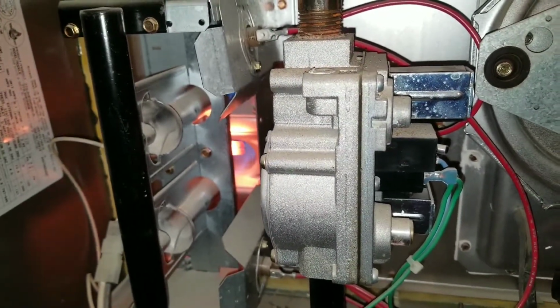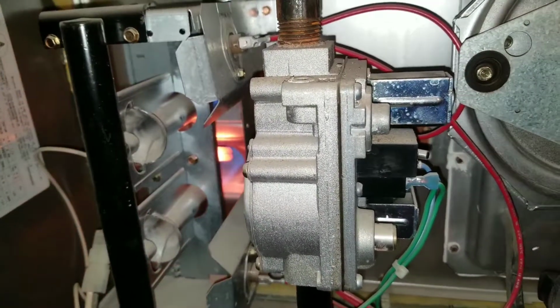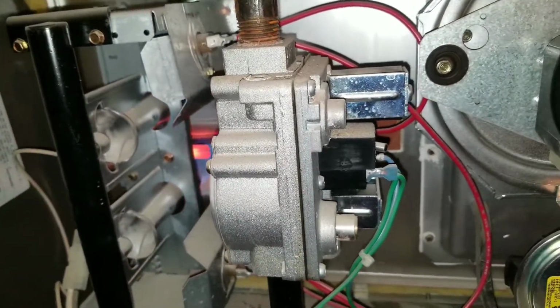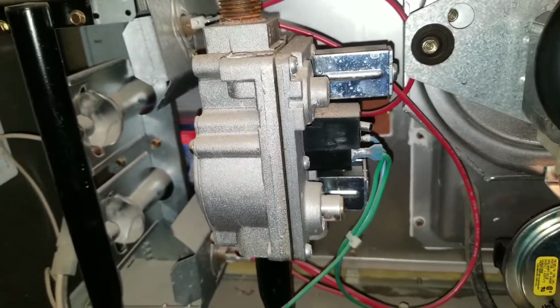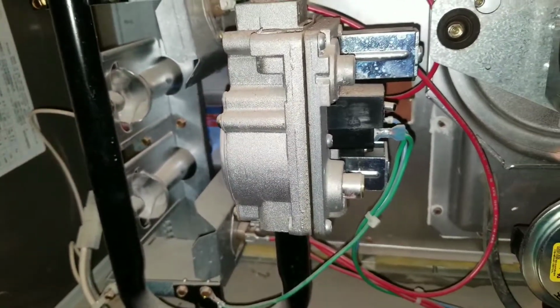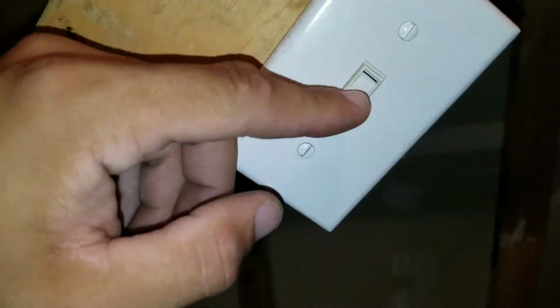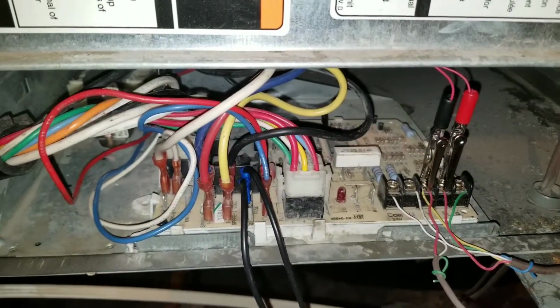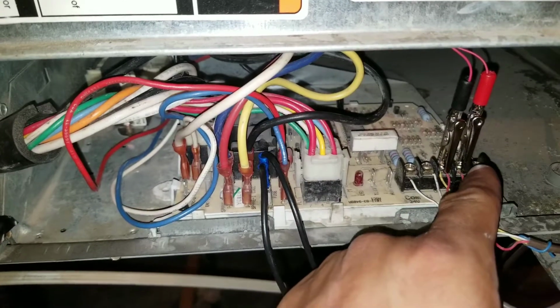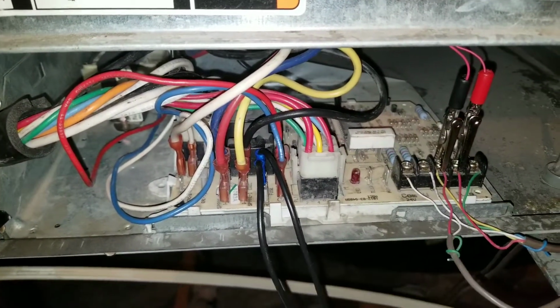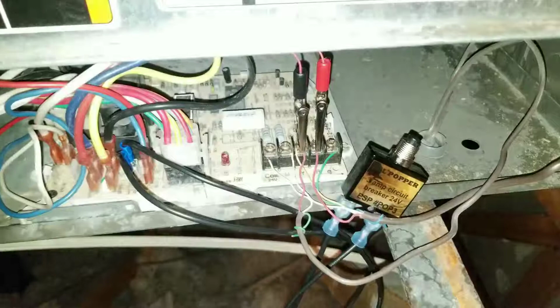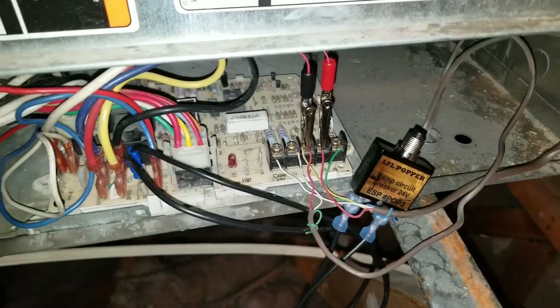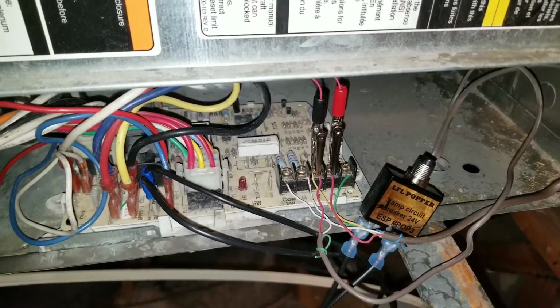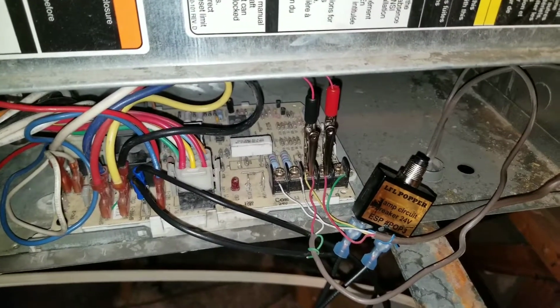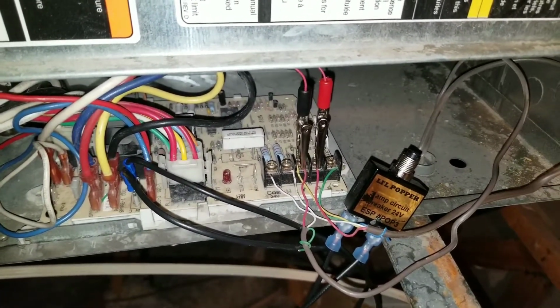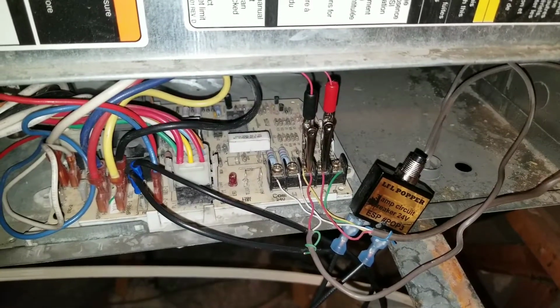So right now, if I was troubleshooting my system and I had a short, I would know at this point my blower motor's working, my heater's working, so that would leave one option left. So here I put my alligator clips to my R, my 24 volts, and my Y terminal. That'll be for my condensing unit. Right now I have my unit in the off position here where my switch is. I'm going to turn it on, and because I created a short, that should cause my resettable amp breaker to pop.